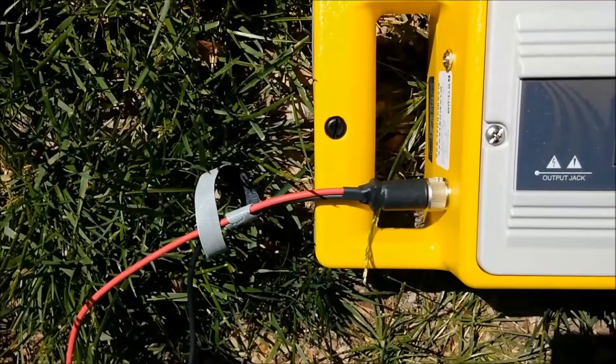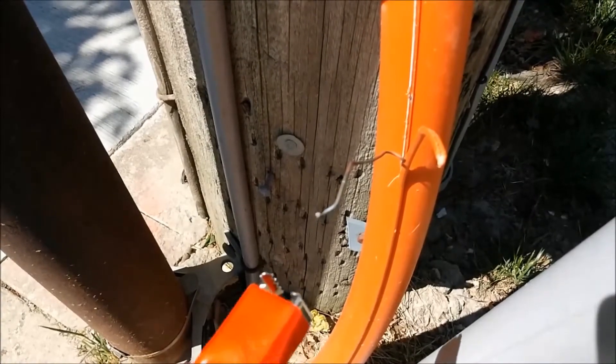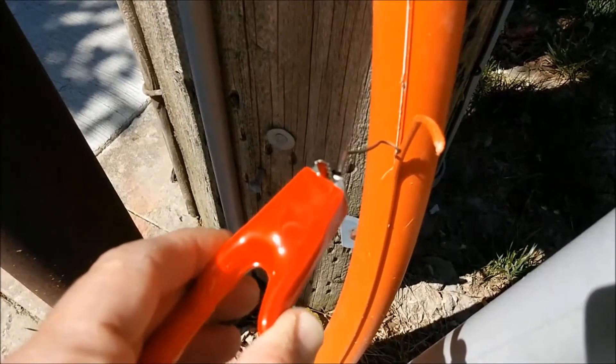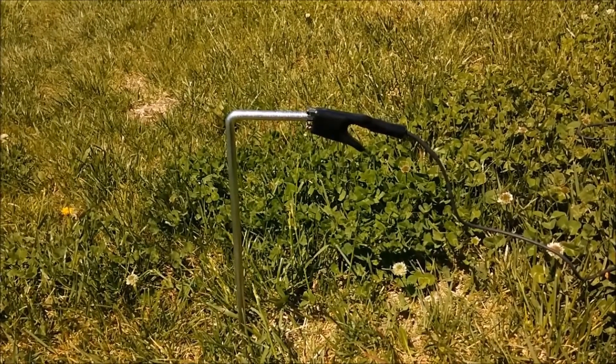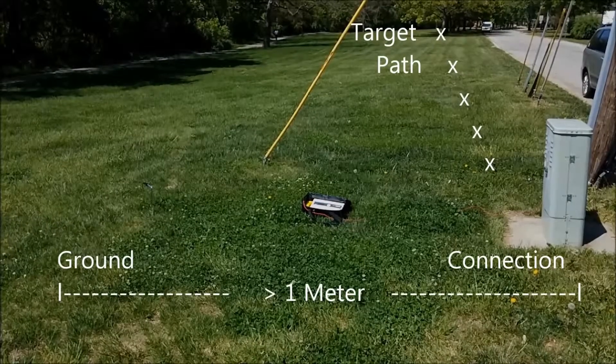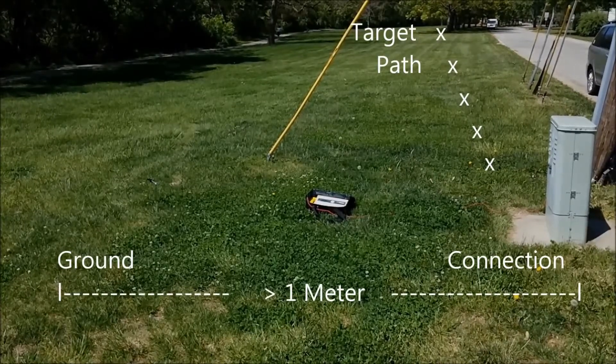To perform a direct connection, plug the red and black cord into the output jack of the transmitter. Connect the red clip to a conductive part of the target utility. Connect the black clip to an independent ground rod placed at least one meter from the connection point and at a 90 degree angle to the path of the target conductor.